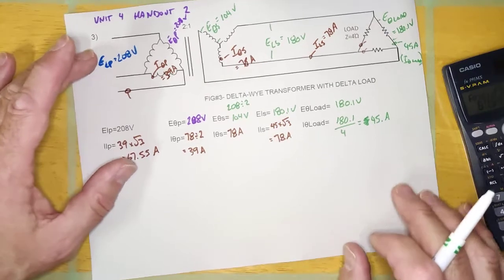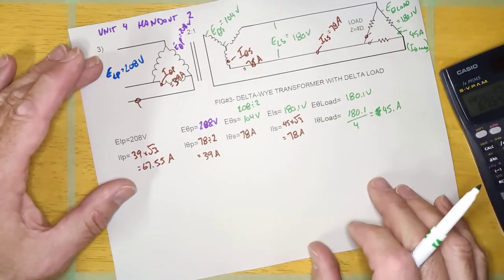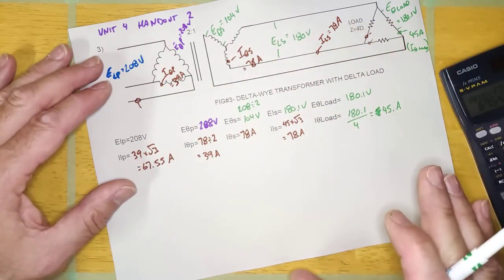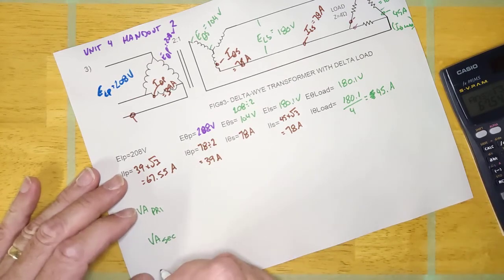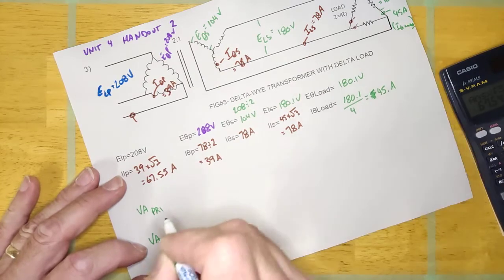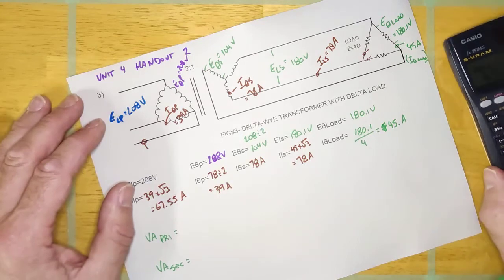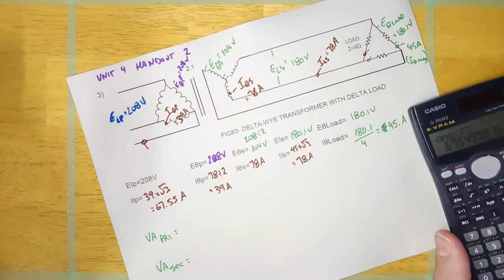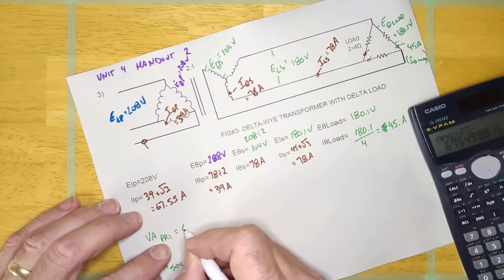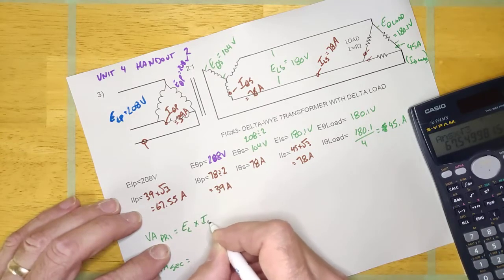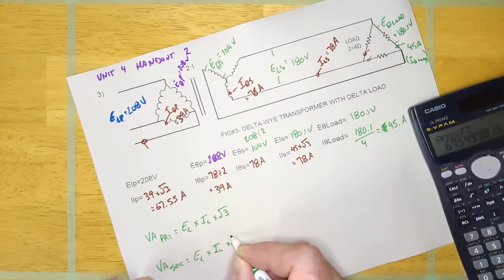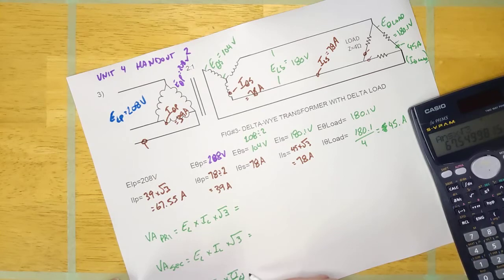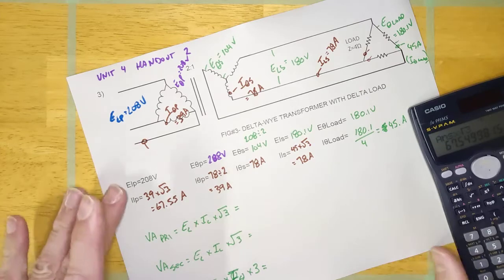When you do these on the test, you must calculate the VA — freaking everywhere. You're going to calculate the VA at the primary, at the secondary, and at the load. You have two different formulas for VA: one uses line values, and one uses phase values. Use line voltage times line current times √3 for the secondary, and phase voltage times phase current times 3 for the load, and I'll tell you why.